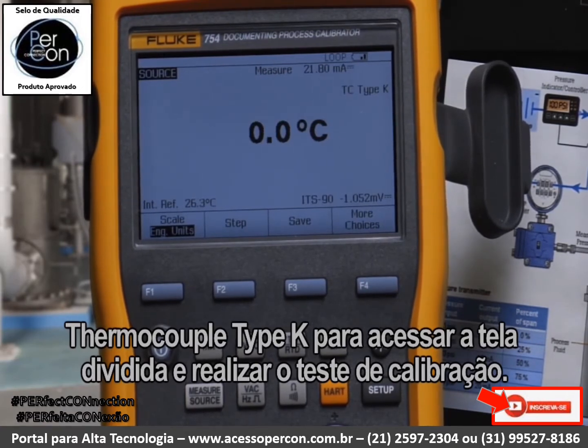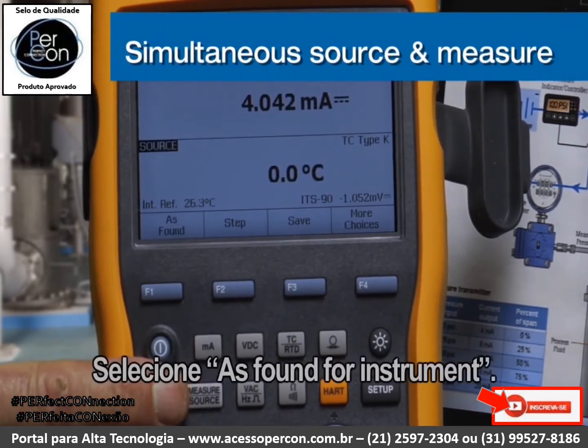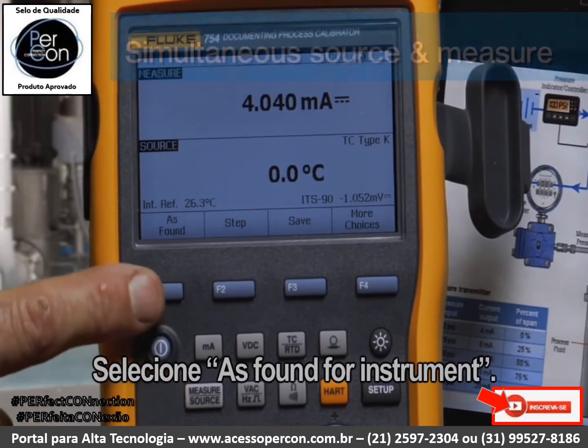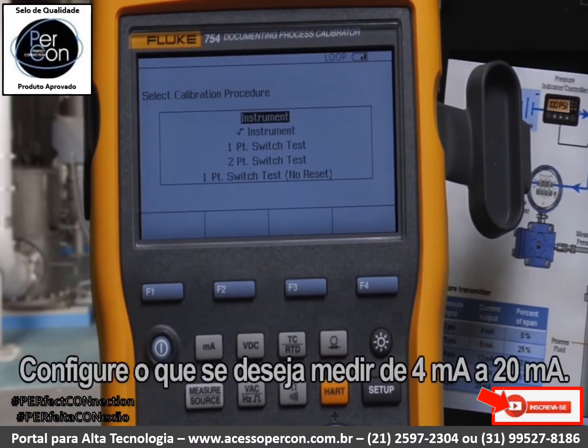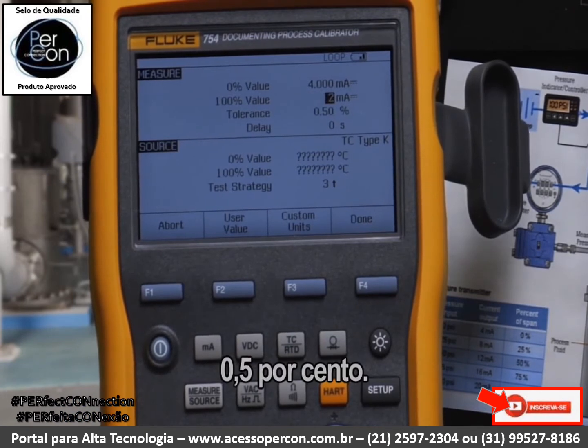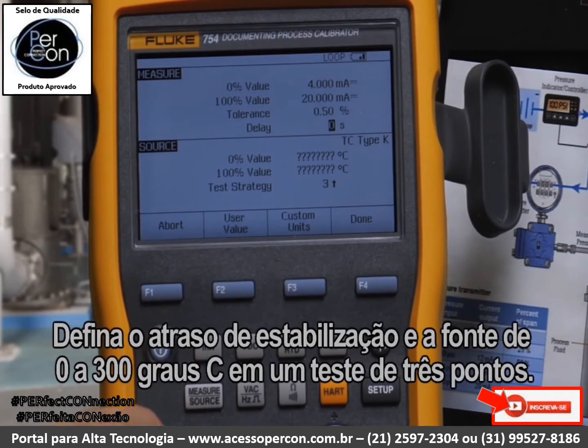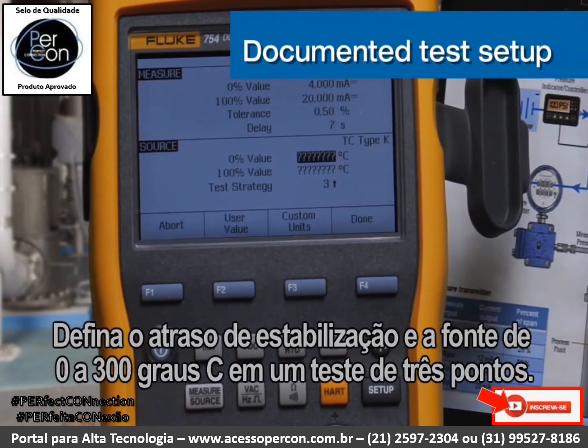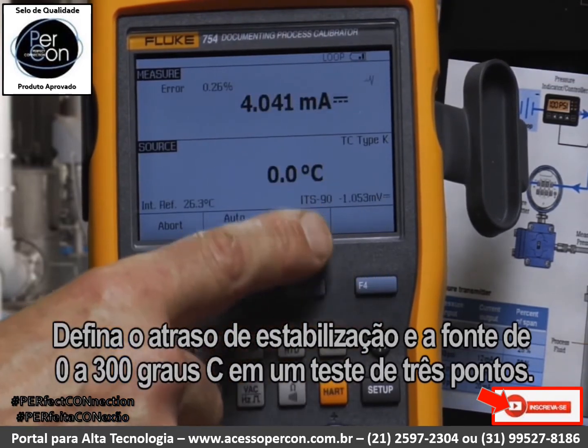Enter the split screen to perform the calibration test. Select As Found, then Instrument. Configure what we're going to measure: 4 to 20 milliamps, with a tolerance of 0.50 percent. Set the settling delay, then source zero and 300 degrees C as the full-scale value, and select a three-point test.